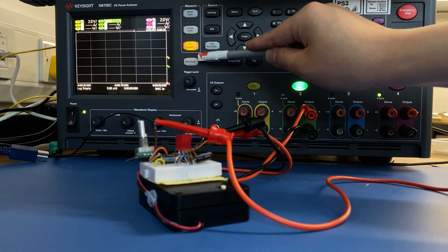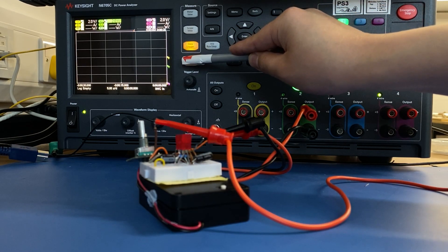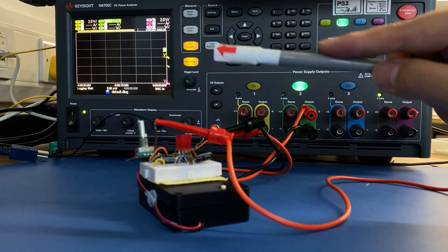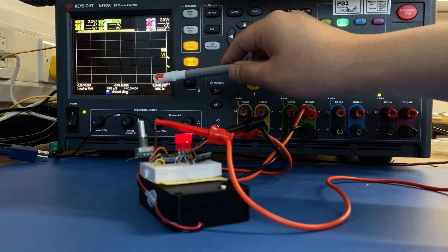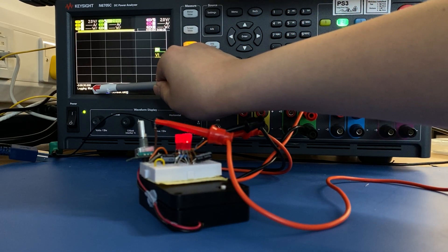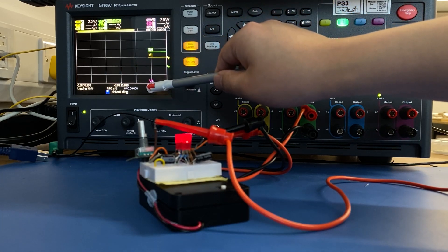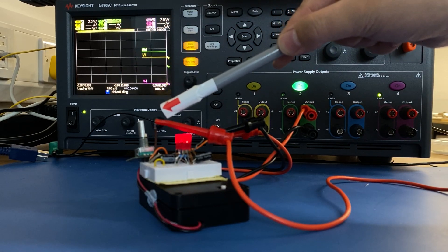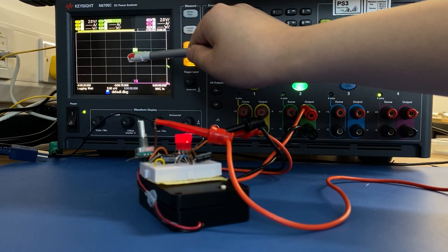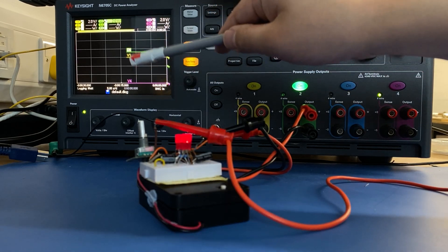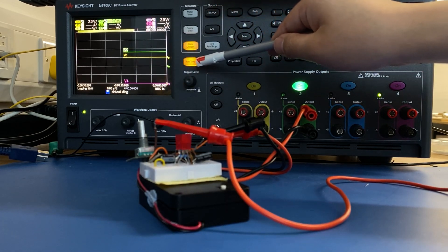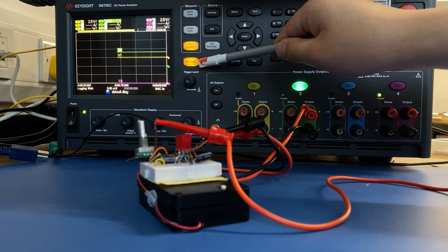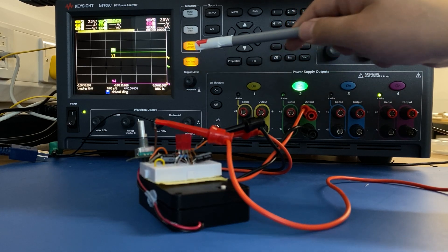And if we start the data logger, you see the logging is waiting. But it's waiting for the trigger signal to be enabled. But the signal captured in here is still captured by the data logger. So you don't need to worry about losing any data.